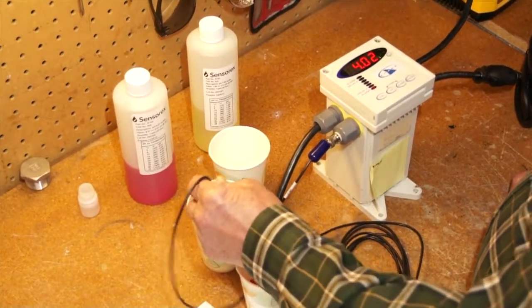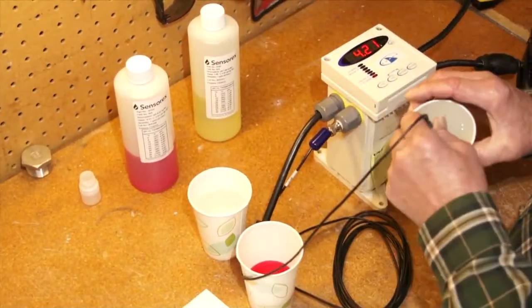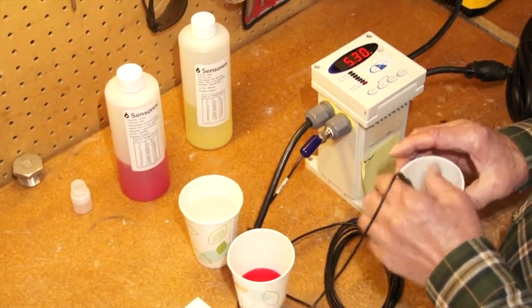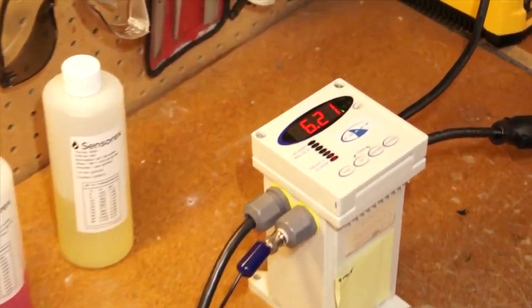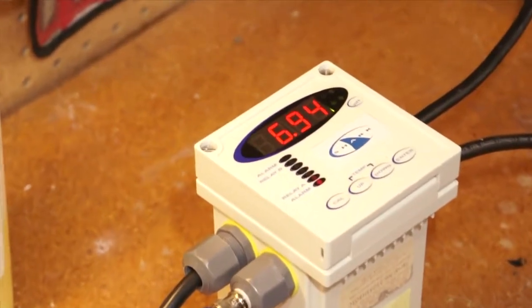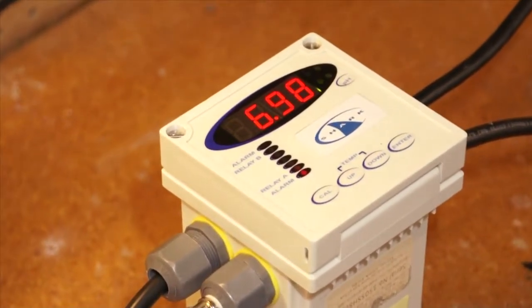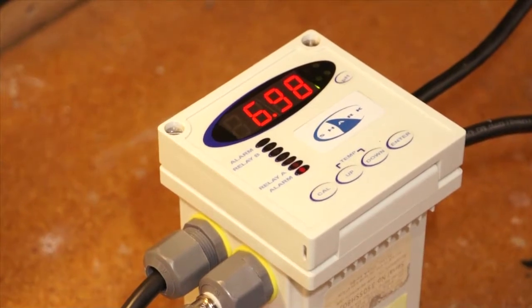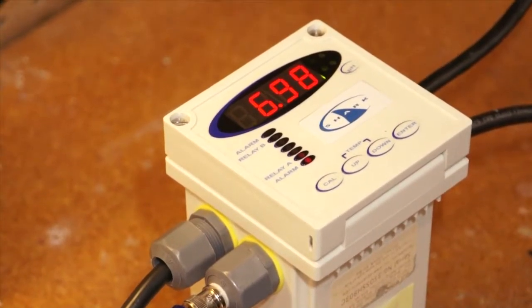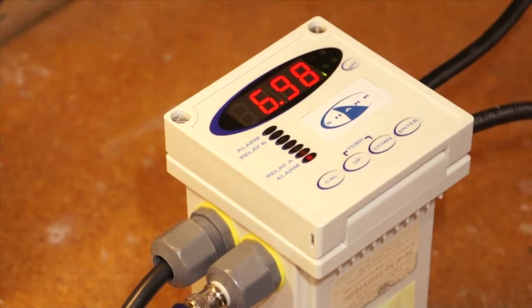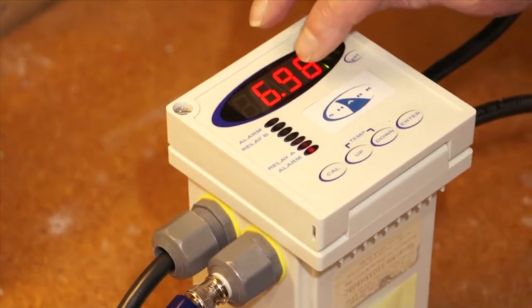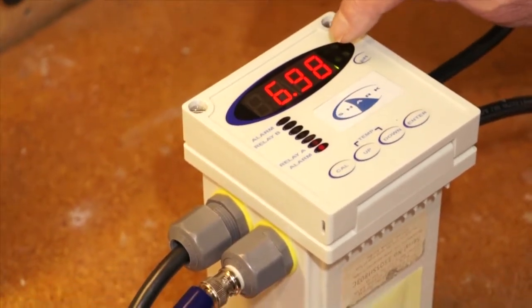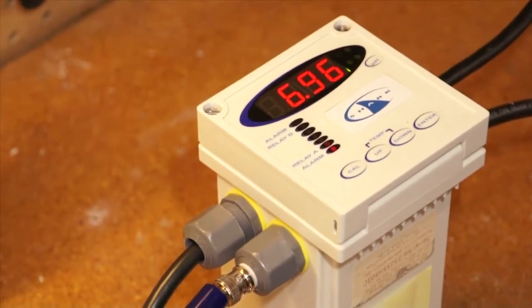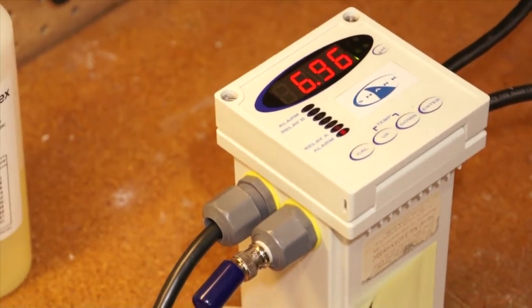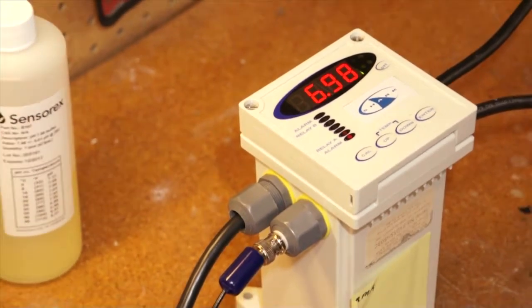So we'll rinse the probe and put it in buffer 7. You see the numbers climbing. And it's 6.98, which is well within the parameters that we operate under. As long as we're within 1/10 of a point, we're fine. We're within 2 100ths, or it's going to flash back and forth, 2 to 3 100ths, and that is acceptable for our system.